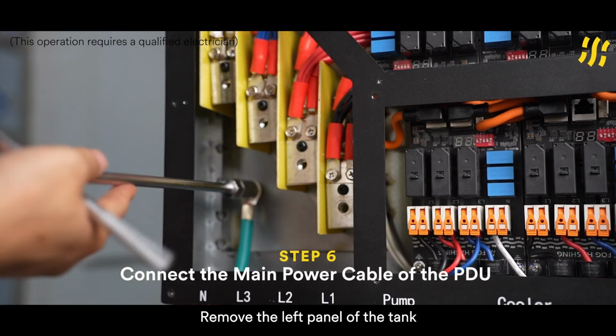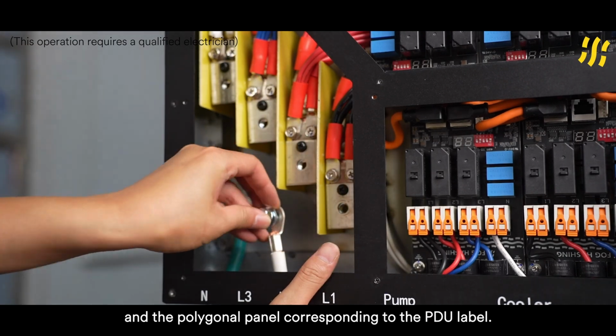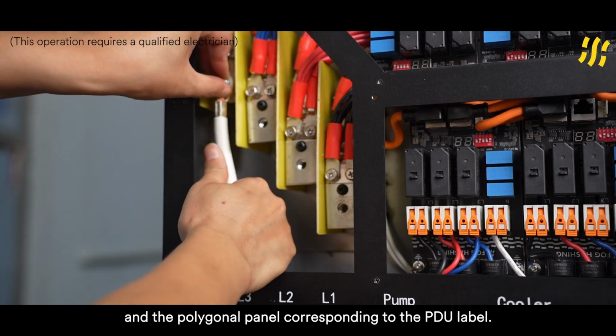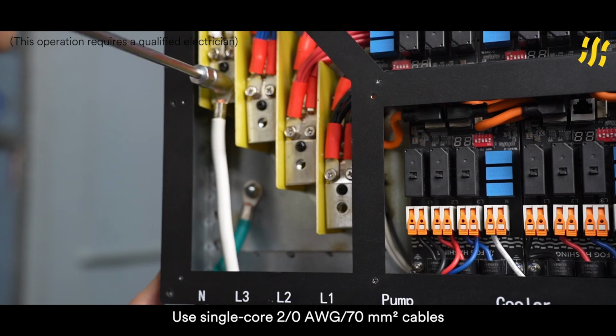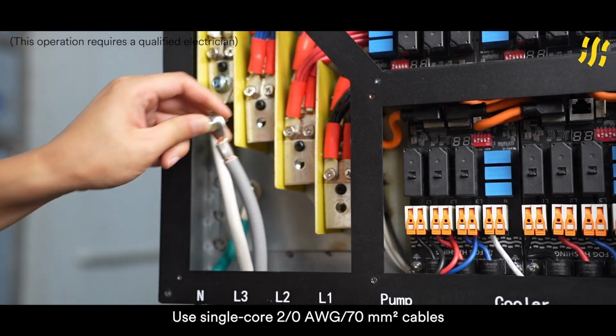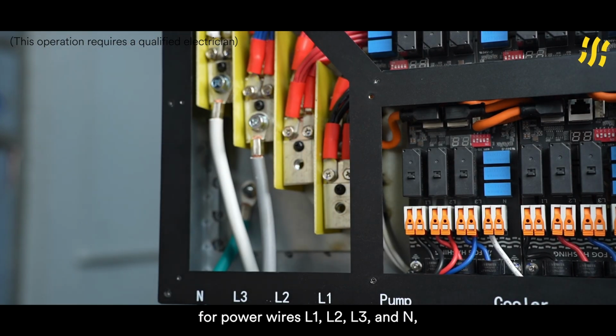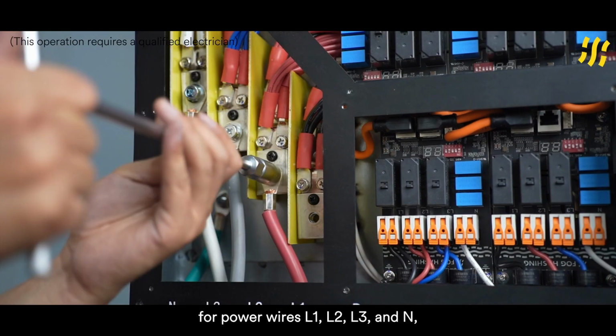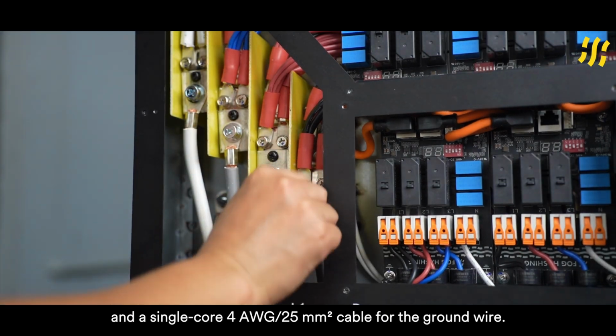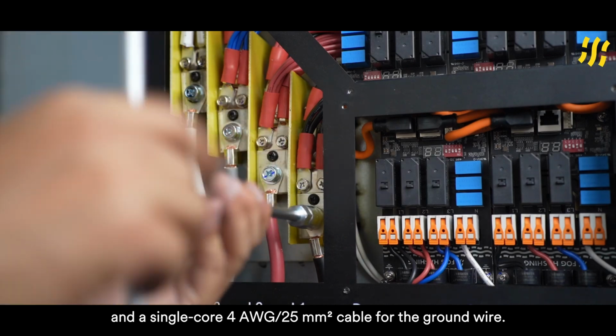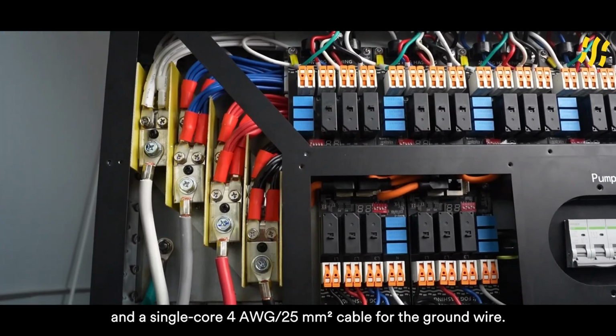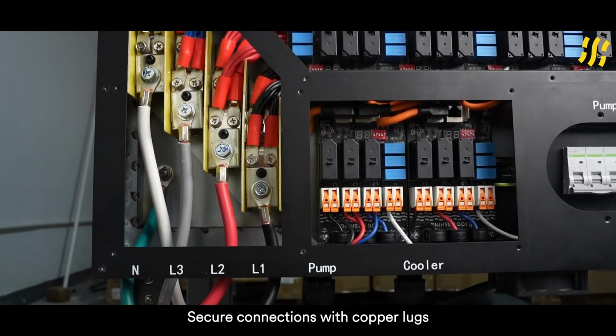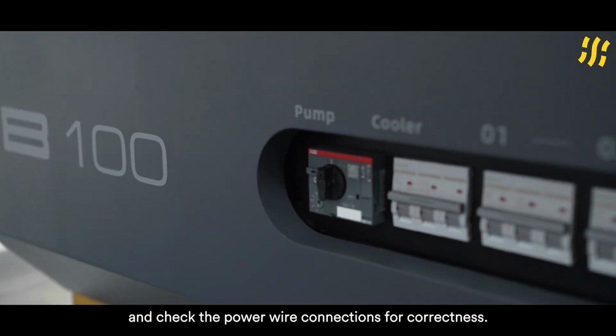Remove the left panel of the tank and the polygonal panel corresponding to the PDU label. Use single core 2/0 / 70 mm cables for power wires L1, L2, L3, and N, and a single core 4 / 25 mm cable for the ground wire. Secure connections with copper lugs and check the power wire connections for correctness.